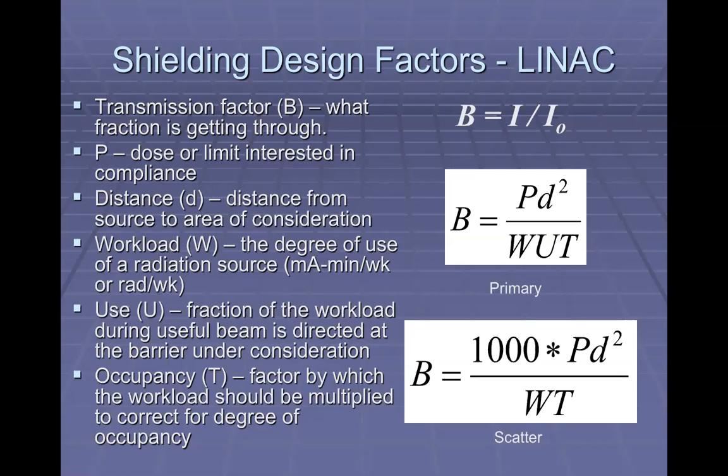If your Linac vault is surrounded by only hallways or only spaces where people are not occupied 24/7, then you can take credit for that, and you can require less shielding, because you know that there's not going to be someone there all day, every day, for every single treatment that is run on this machine.